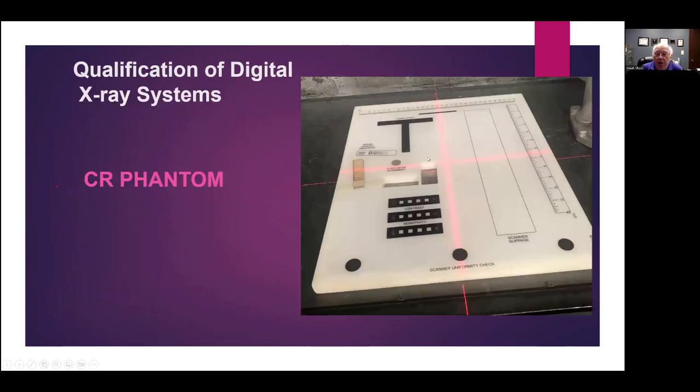So here's a typical E2445 Phantom. It has different features embedded in it. It's got a laser jitter T. It's got contrast blocks and different materials. It's got uniformity checks. It's got bands for checking slippage and banding. It's got distortion, so you can have measurements in two directions and calibrate that way. And you have your E2002 gauges.